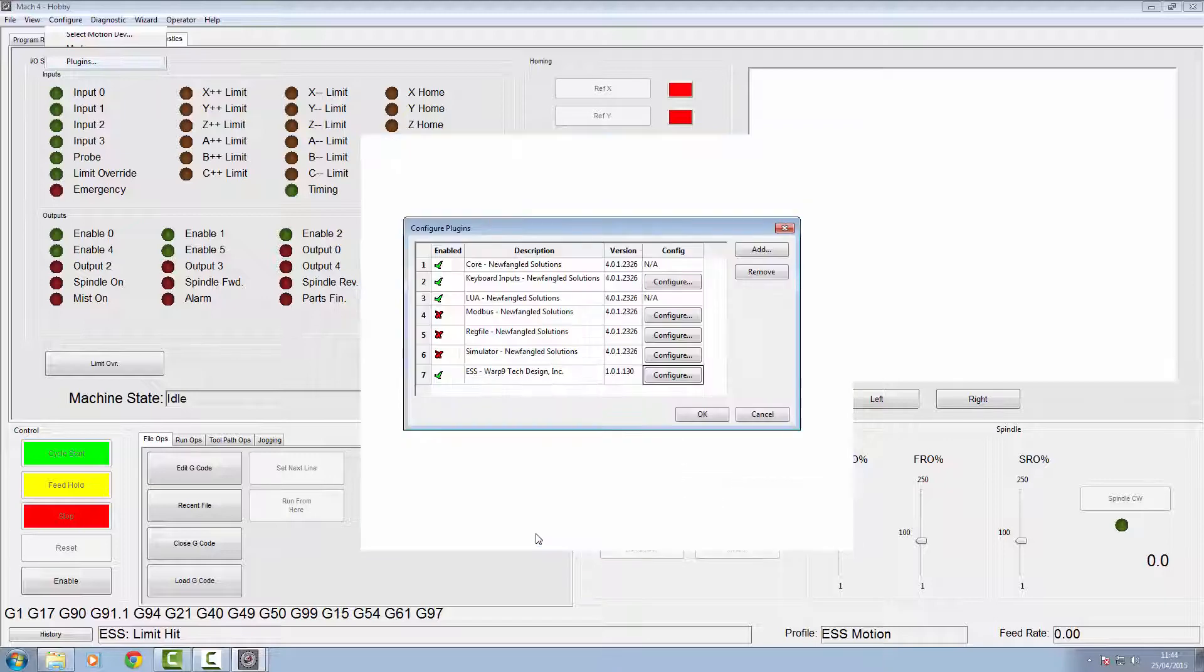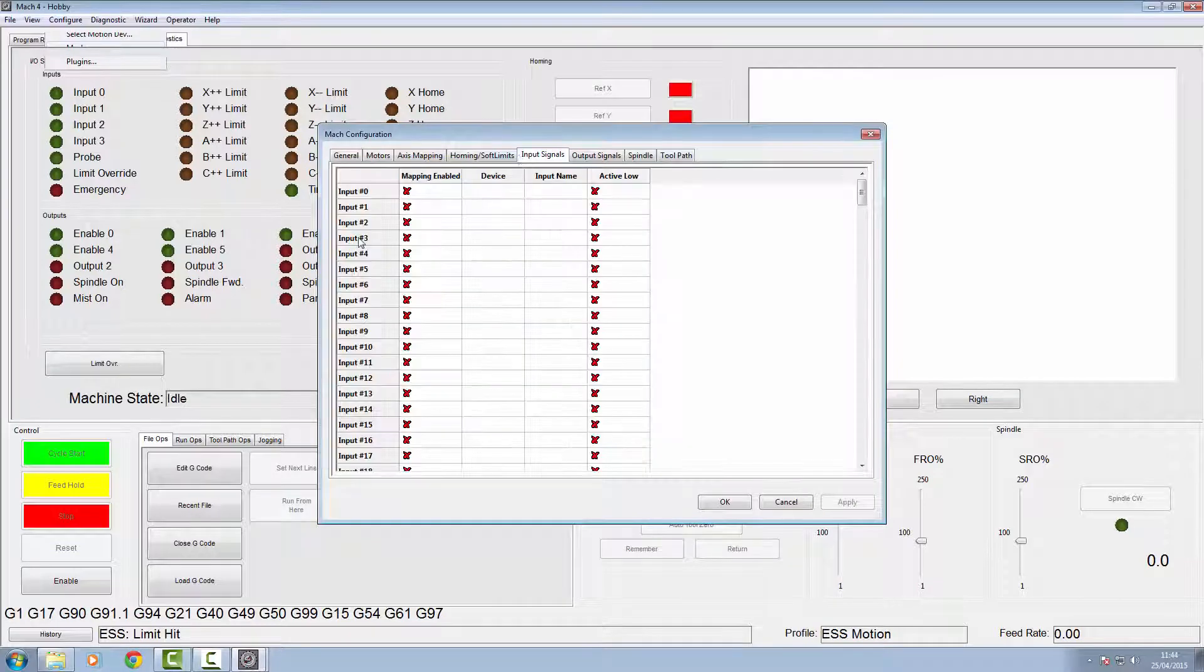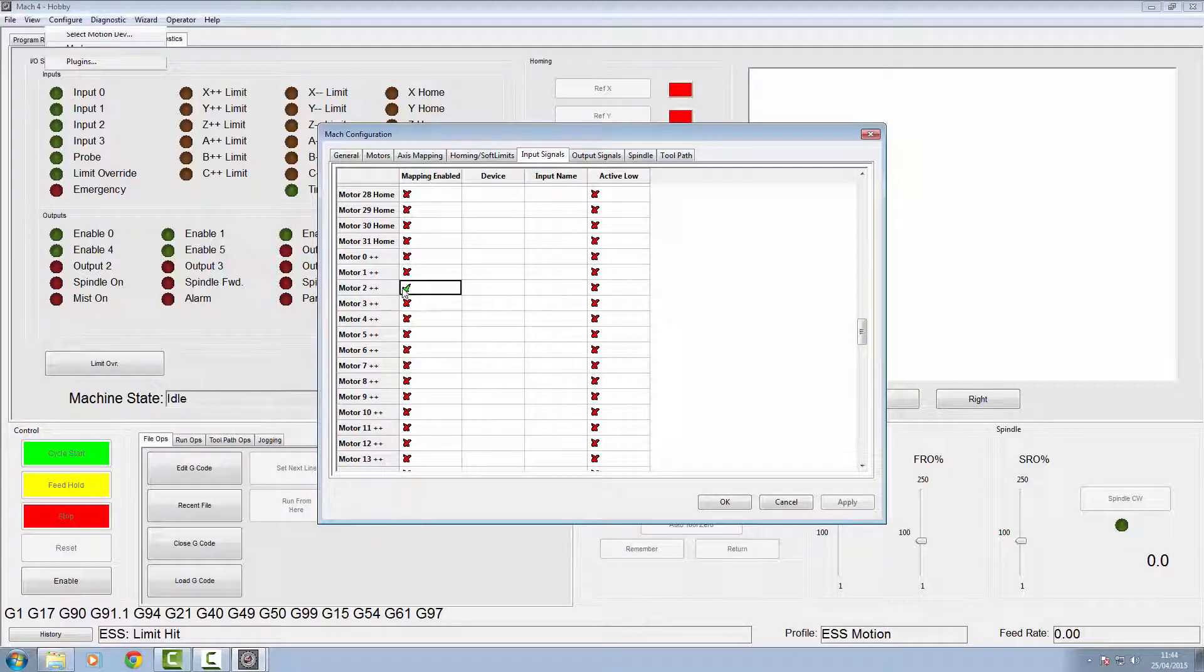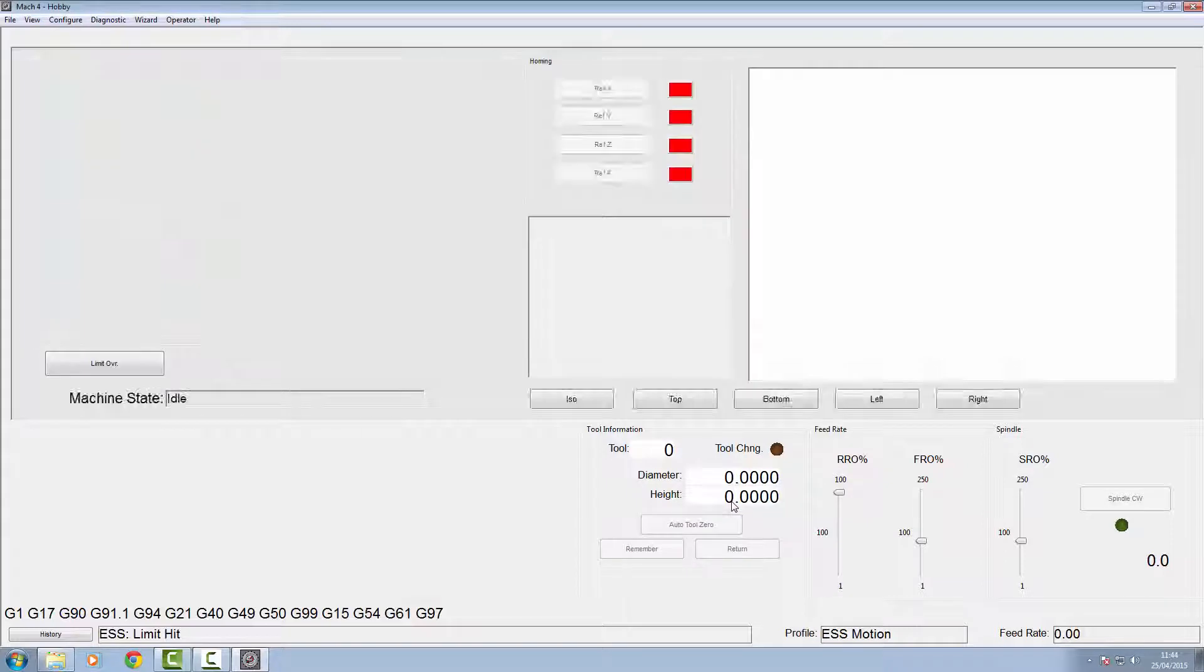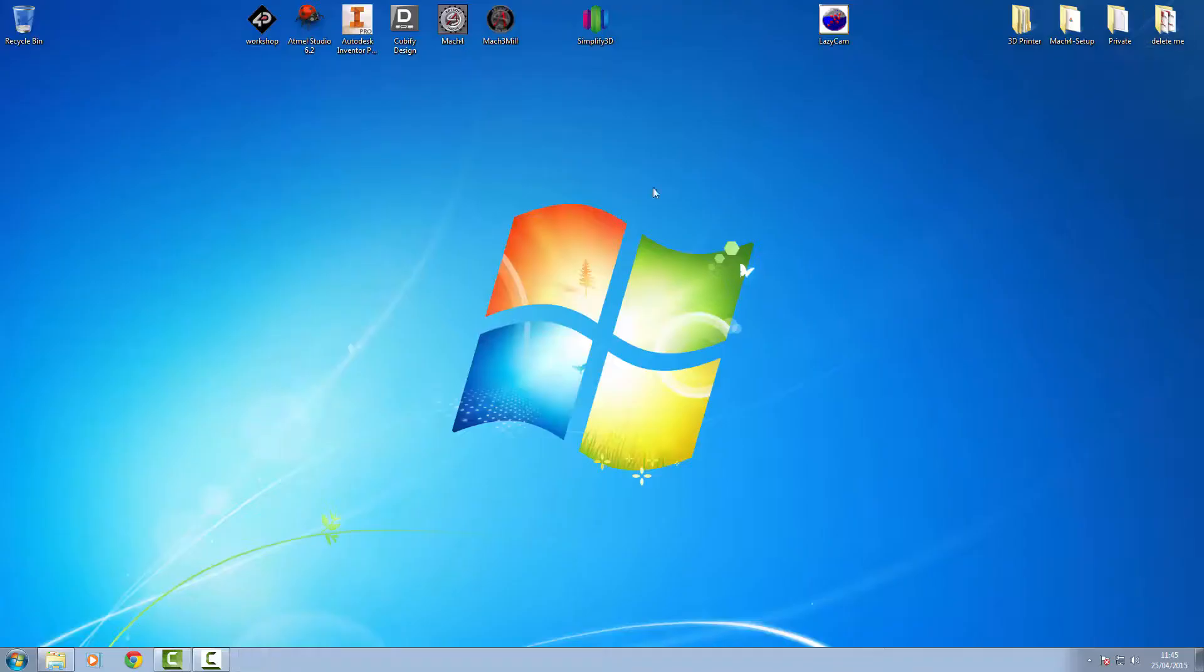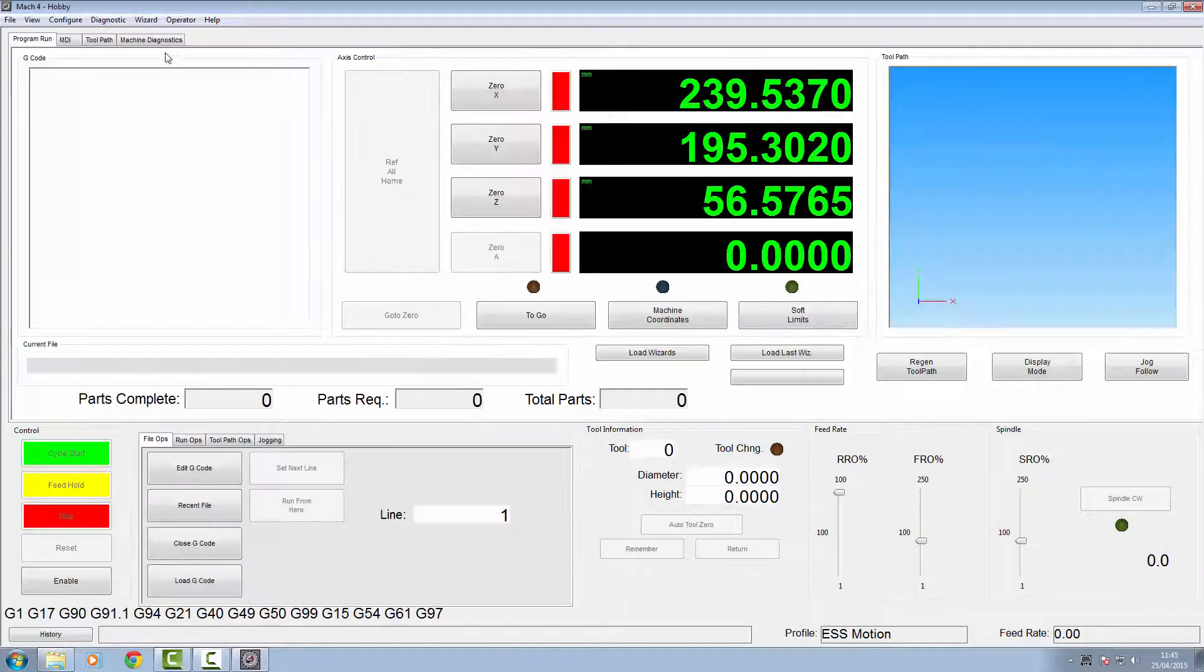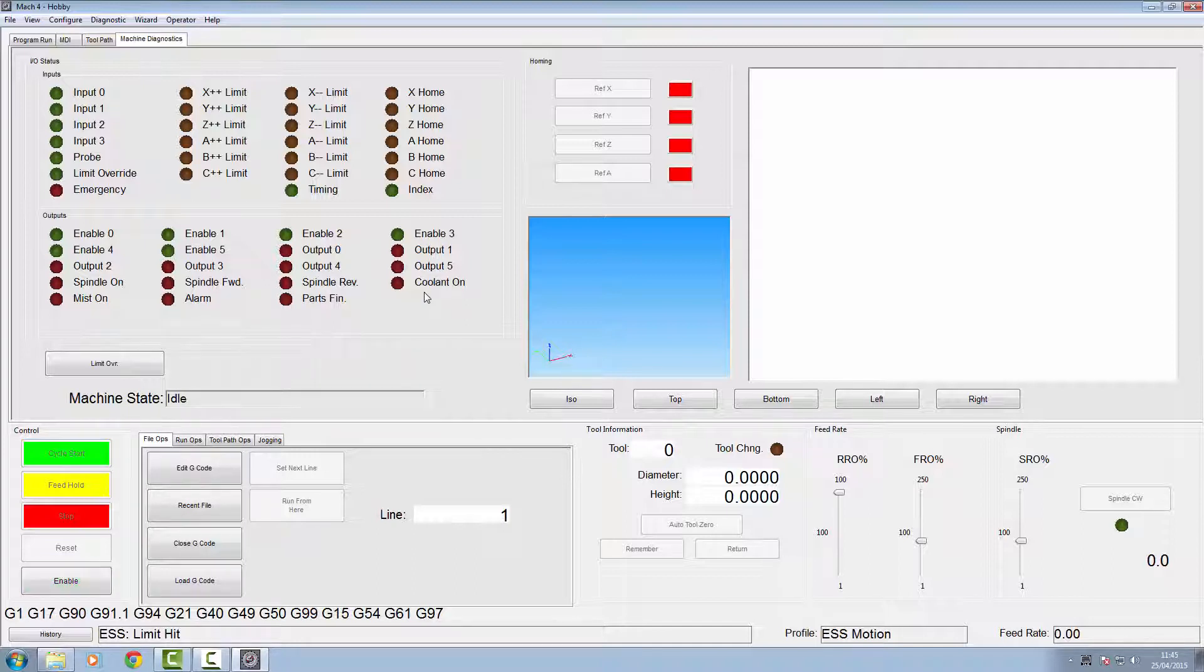We'll click apply, go back into our Mach configuration input signals, find the motor with the plus this time. Motor number two coming from the motion controller, we're using motor two plus. Click apply and OK. Same again, back on the machine, check the switch. Once again she's done it, this does get a pain when you're doing this, but once it's done this doesn't happen anymore. Back into our machine diagnostics, check the switch, and that's it. The Z is now working, so all three limit switches are all set.